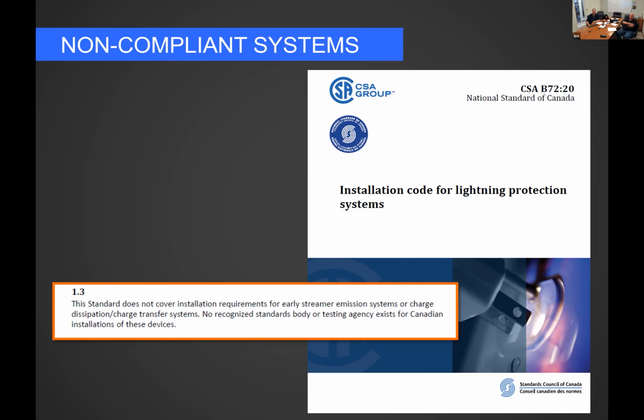So a while back you were talking about where your down conductors were running, and you had main conductors within 450 millimeters. So you were talking about the equipotential bonding. Will that be done with a secondary conductor or a primary conductor? The way B72 is written, I believe the equipotential bonding, if it's a secondary connection to a single item, you can get away with that smaller cable, smaller connectors, no big deal. If you are doing a loop of equipotential conductor to interconnect all the down conductors, that has to be a main-sized cable. Good question, yeah, that's definitely something to be clear on.